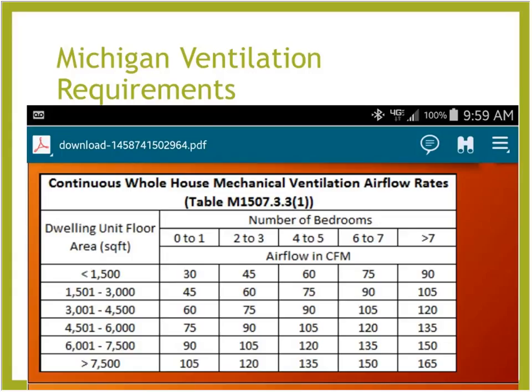So it's really, really important that we make sure that we do meet those efficacies, because we are required when we're doing the inspections to verify that. So make sure that the builders have the literature to provide to your inspectors, showing what that efficacy is, so that you don't run into a problem at the end of the cycle when they're evaluating your ventilation fans. Okay, can you go over quick again what the requirements were for bath fans, inline fans, and ERV? What were those numbers again?